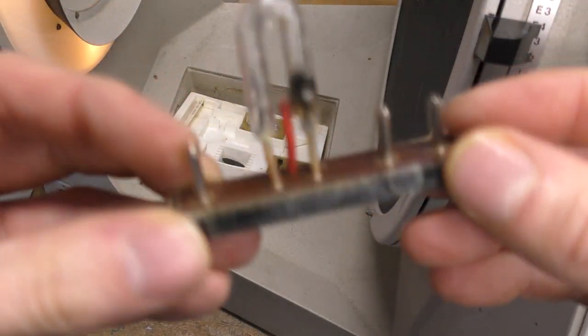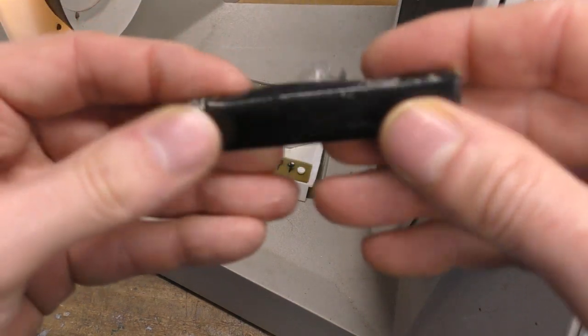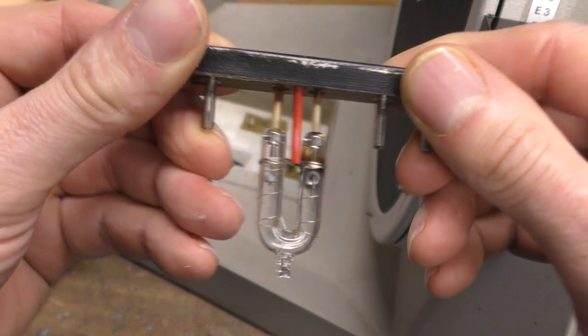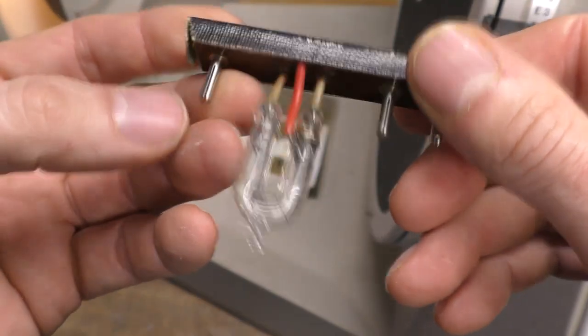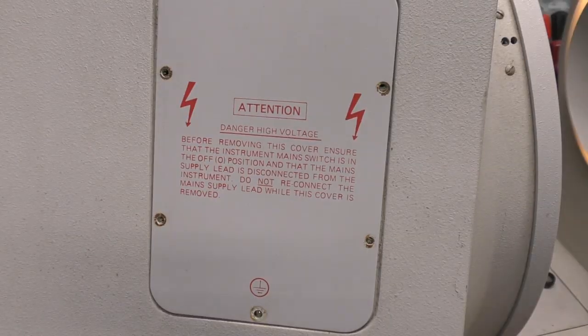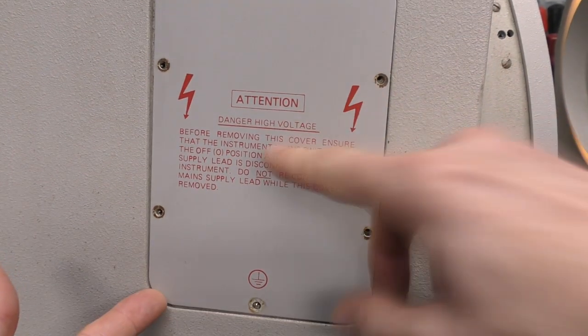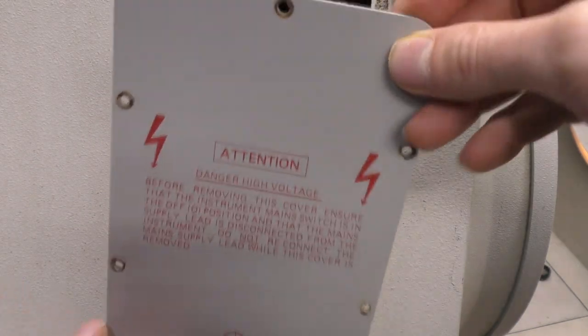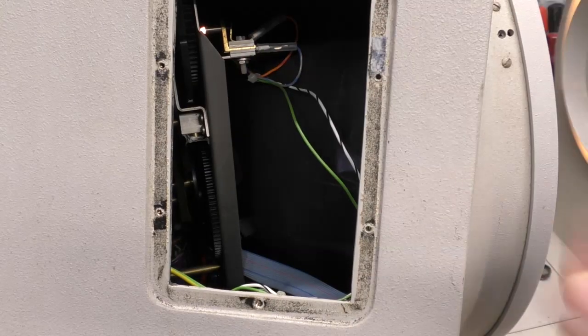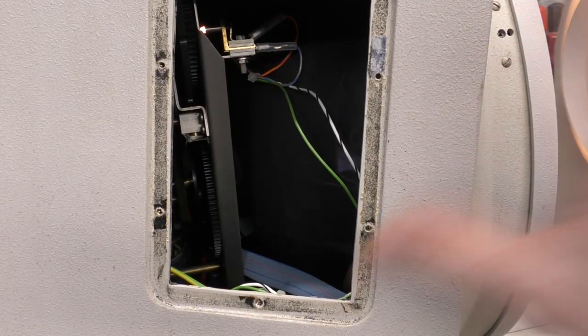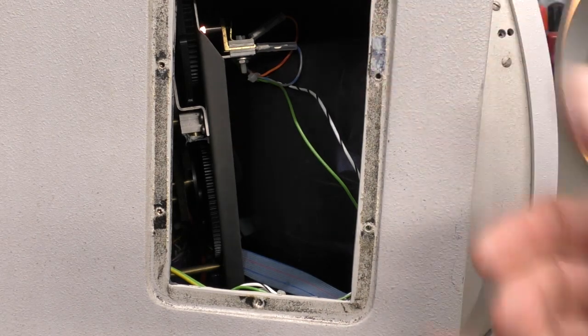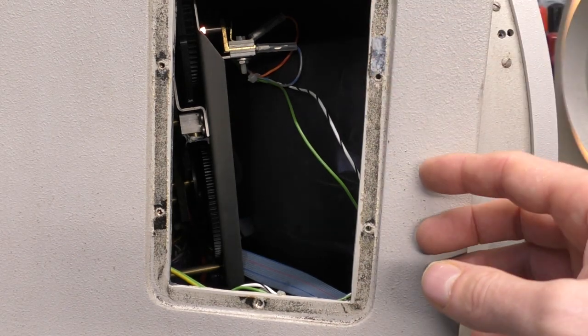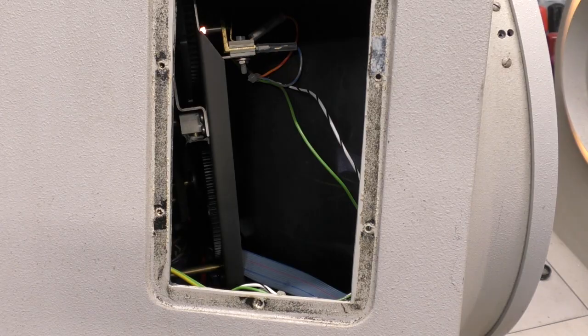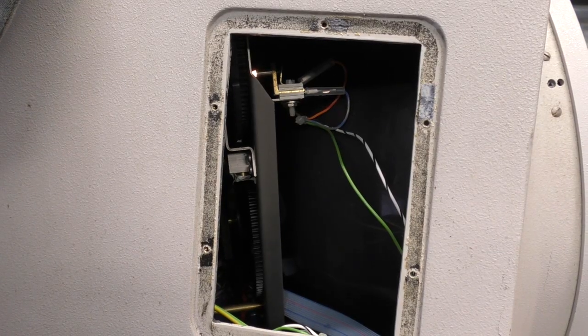This is just a fairly standard, small xenon tube mounted on a plug-in assembly, and this is designed for easy access. This can easily be replaced. And there's an access cover on the side with high voltage warnings, but there's no interlock switch on this. If there's a cover like this on a more modern piece of equipment, you might expect there to be some sort of interlock to turn the mains off when the cover's removed. And you can see the lamp flashing.